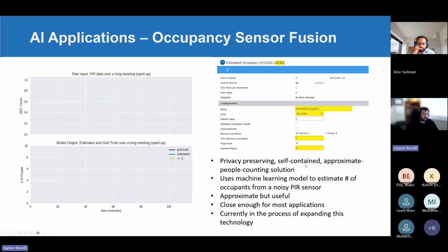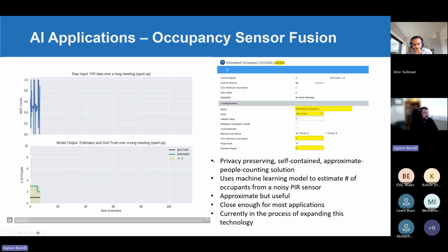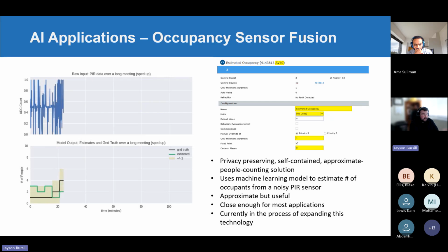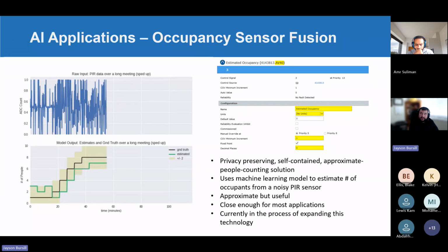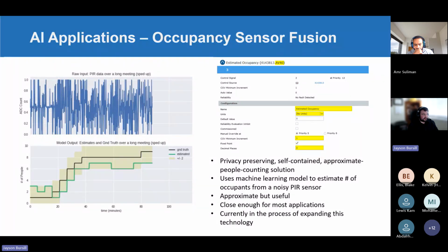So in this case, kind of taking this thing and encapsulating it as a BACnet object, the reason this has to go on the device is because of the rate at which the analog to digital count from the passive infrared sensor varies. So you have to do something called downsampling in this case, which is you look at the passive infrared sensor reading, which comes in at sub-second intervals - we're talking like 20 times per second. And then that gets smoothed out a lot, and that's kind of the main input to this particular system to estimate the occupancy count over time.